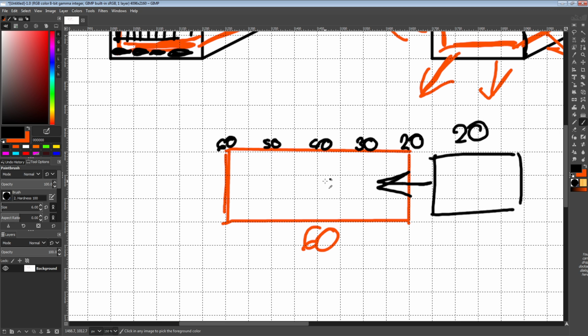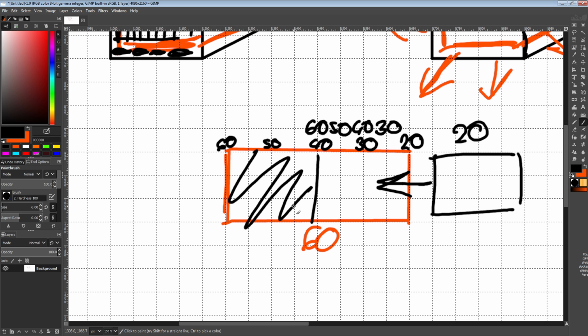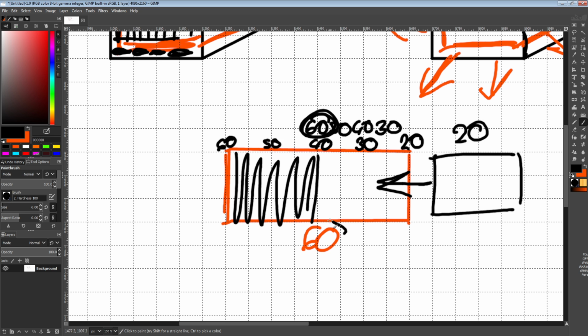But it gets worse as you lower the airspeed, because instead of hitting 60 degrees by the end of the fin stack, you might hit 60 degrees by the middle — and then the end of the fin stack doesn't do anything anymore. That's literally wasted surface area, because the air has reached the same temperature as the fin stack. They're at equilibrium; no more thermal transfer can happen.